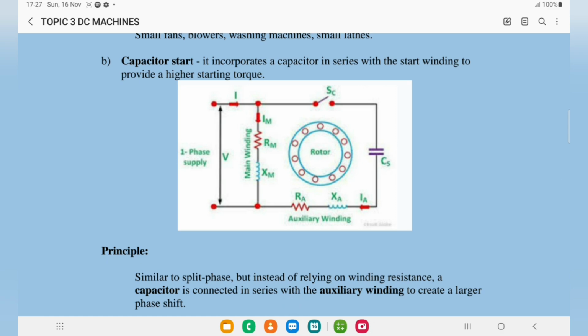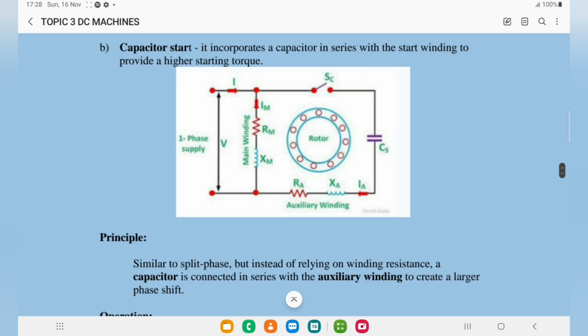As for the capacitor start, you can see the circuit there. We have the rotor, we have capacitors, we have a switch, we have the main winding, we have the auxiliary winding, and we have the phase supply. So this method involves a capacitor that is in series with a start winding. That capacitor is necessary for providing that high starting torque, that high starting momentum, in order to allow the motor to start rotating.